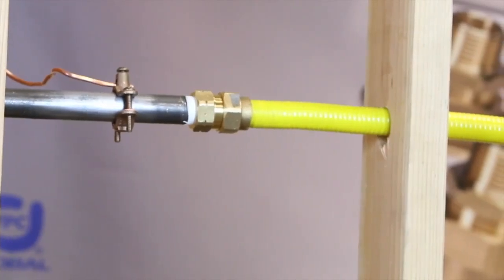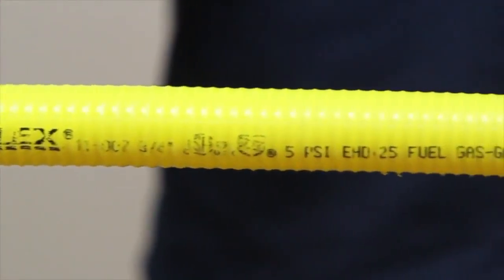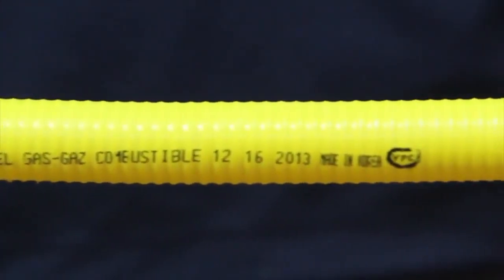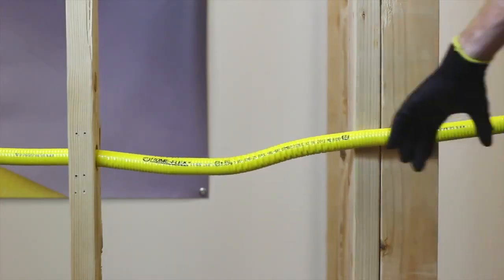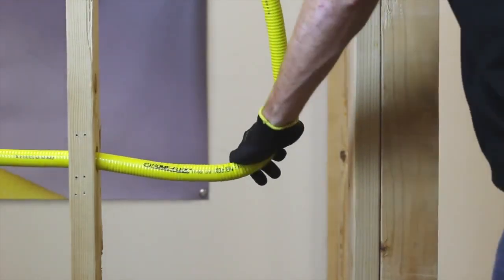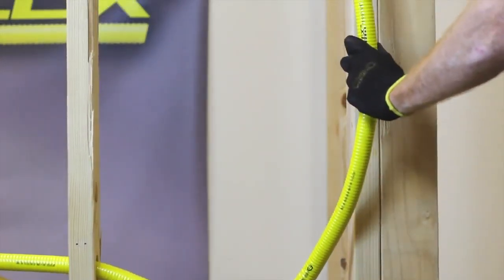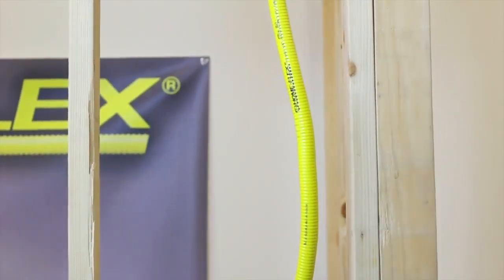When systems are not properly bonded, the current from an energized line can cause electricity to arc or jump from one system to another and damage the CSST. Proper adherence to the bonding instructions should significantly lower the risk of electrical arcing and related damage to CSST.